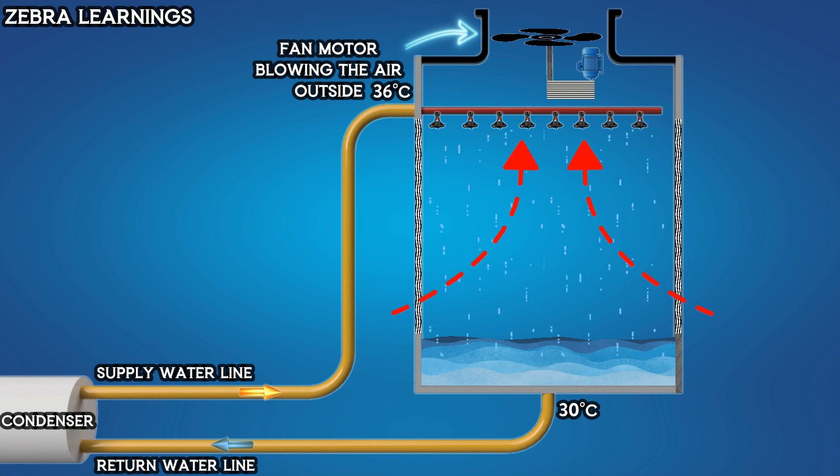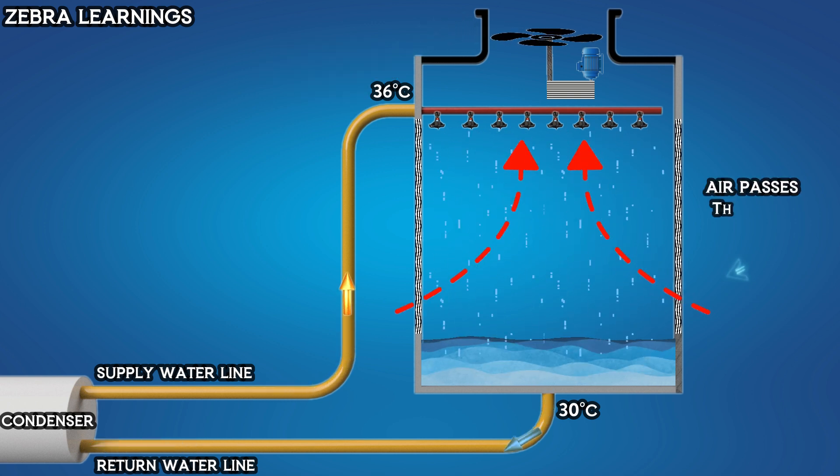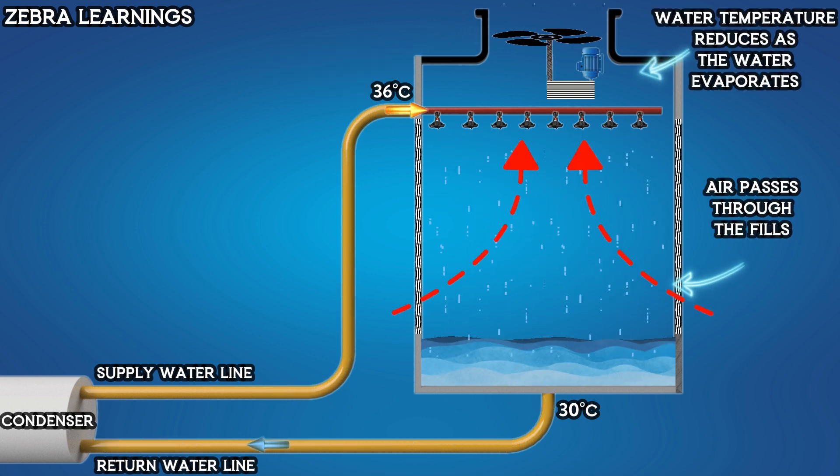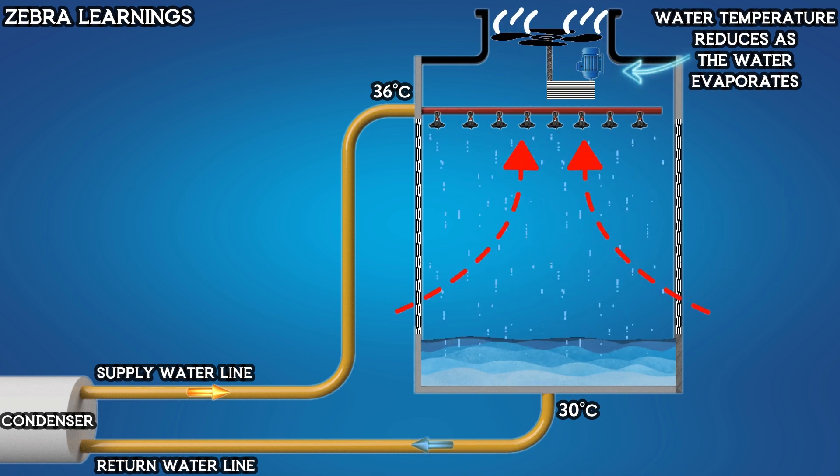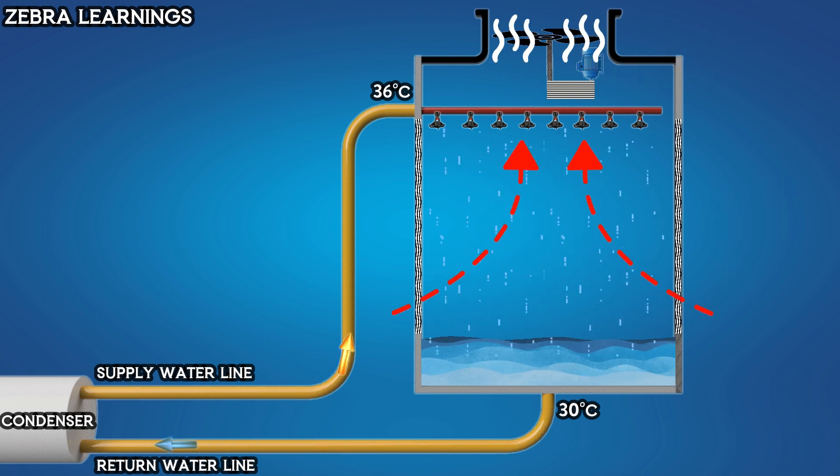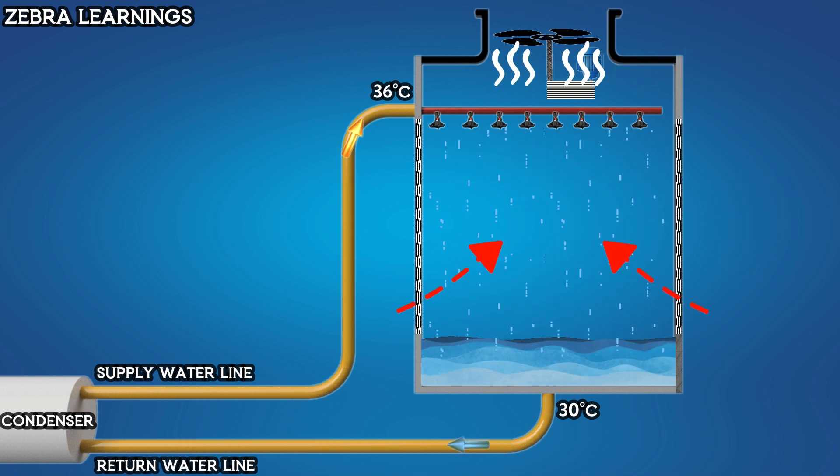The fan motor in the cooling tower draws air upwards through the fills. As the air passes through the fills, some of the water evaporates and is carried away by the air, cooling the water. This cooled water is then returned to the chiller.